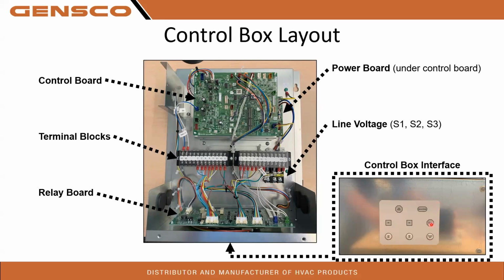On the outside of the box is this little control panel right here. This thing has a couple different buttons on it that we'll get into. This thing is used for test operation only. Apologize, there are a couple of LEDs on there. So these upper, what look like buttons, are not buttons. They're just LEDs for W1, W2, depending on which one's being used, which one's going to be lit up. Then you have normal operation, which will normally be lit up green, test mode, and emergency operation. So if your heat pump's not working, anything like that, and you're curious to see if the system is actually in emergency operation, this little light right here will be lit up for you.